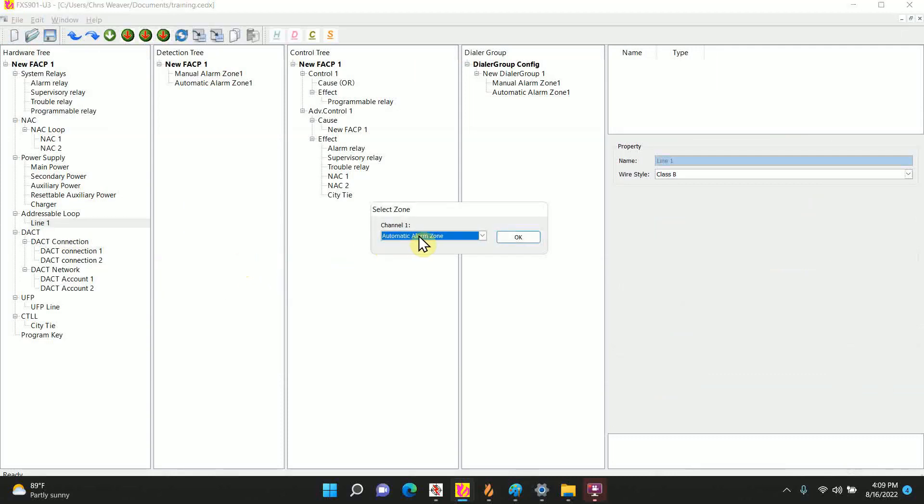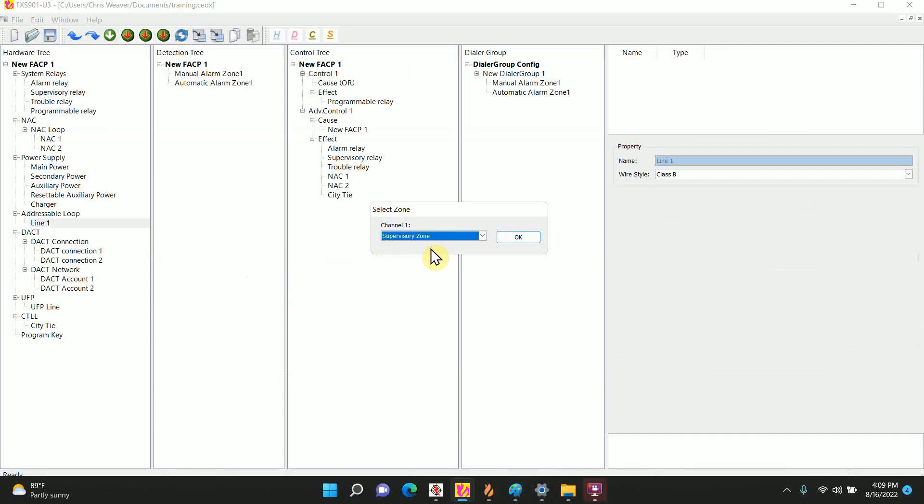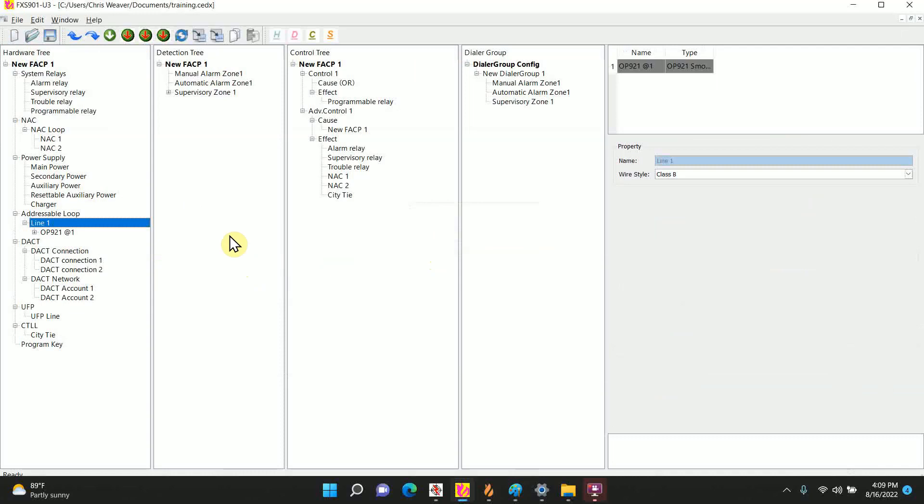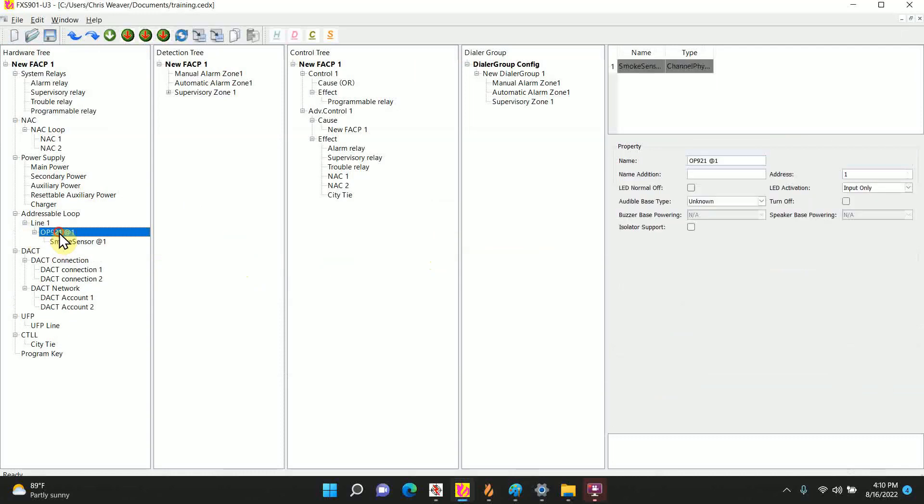OP921 gives you an option of how you want this to behave, an alarm, or in this case we want a supervisory. We do not want our duct to set off the alarm. Hit OK and I'll add it in. But right now it's just a smoke.